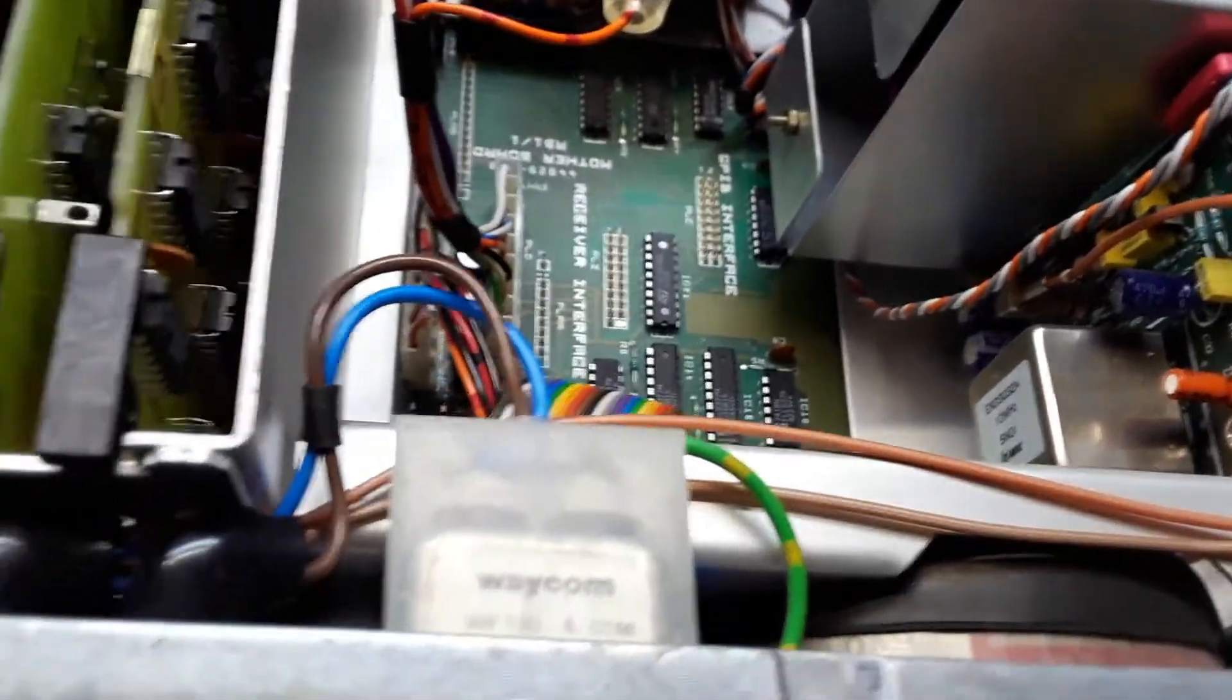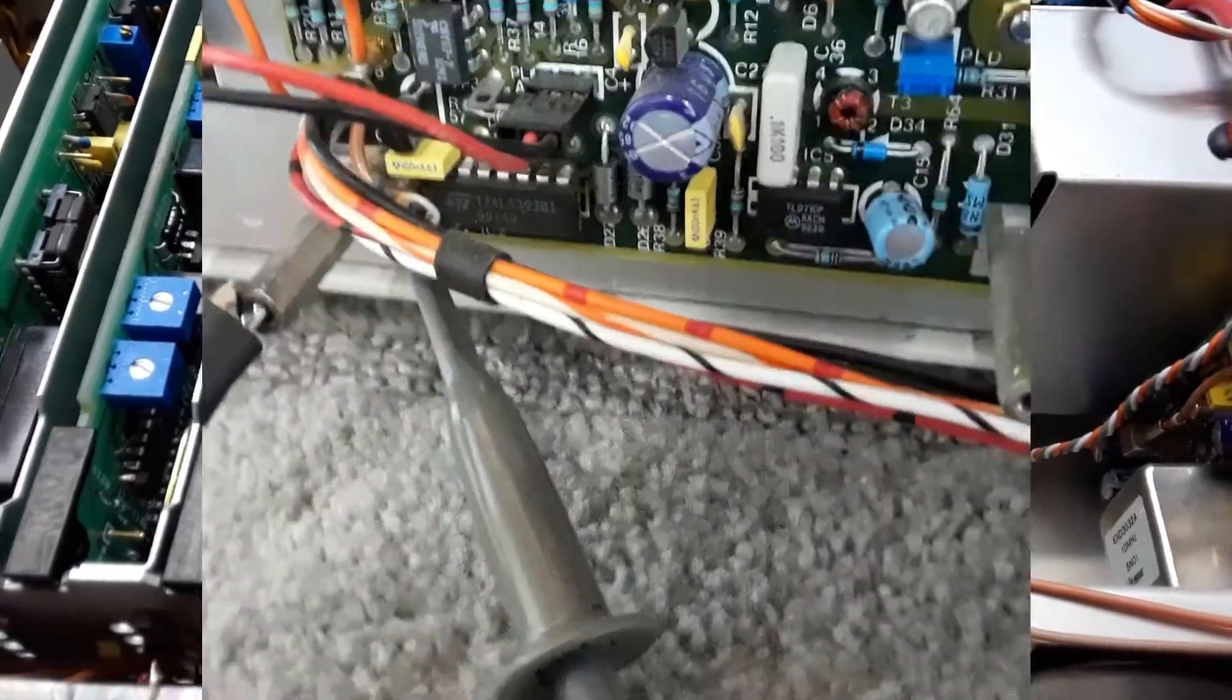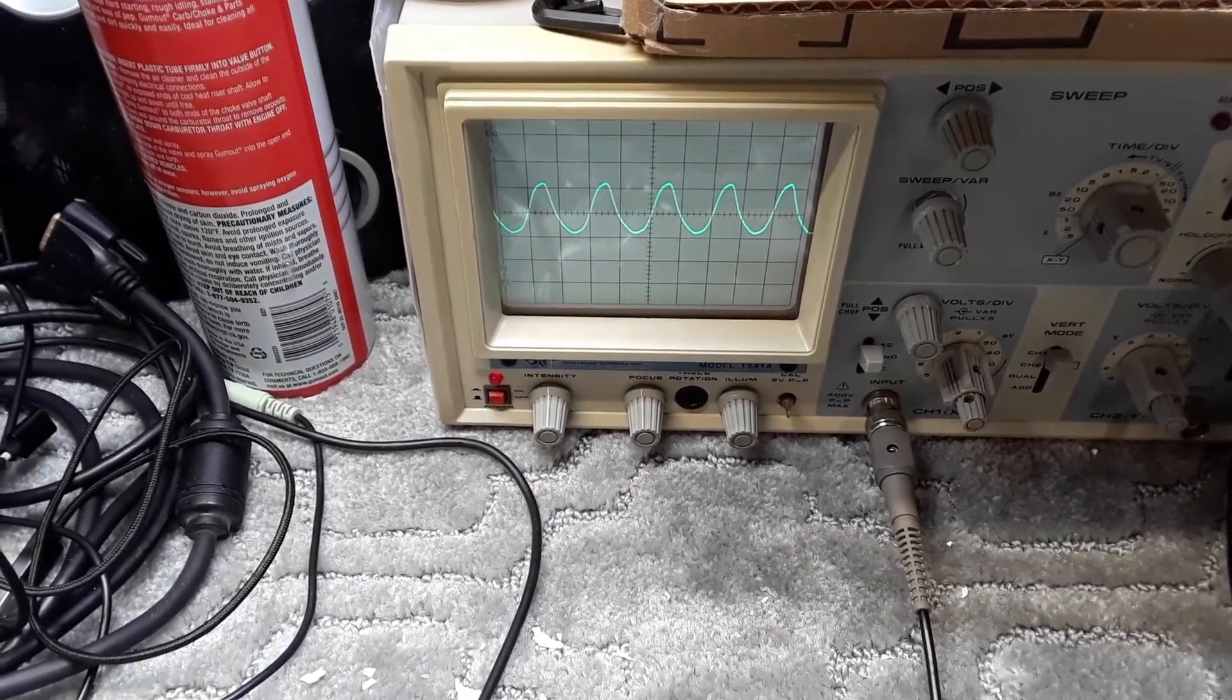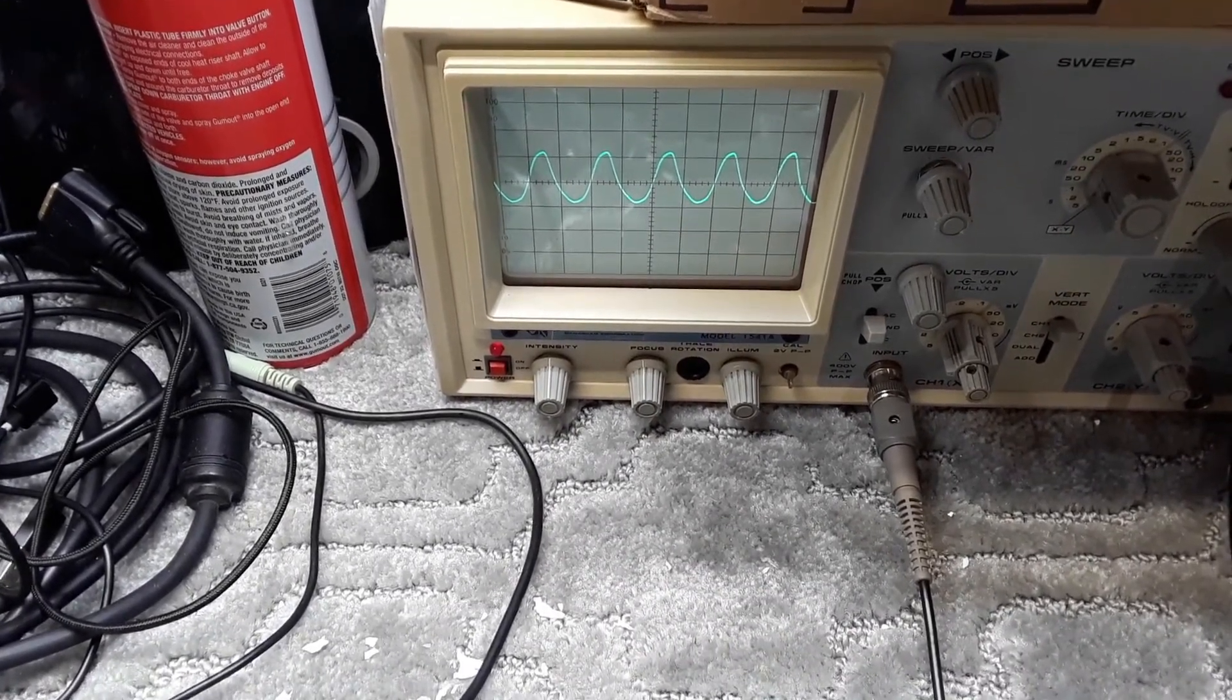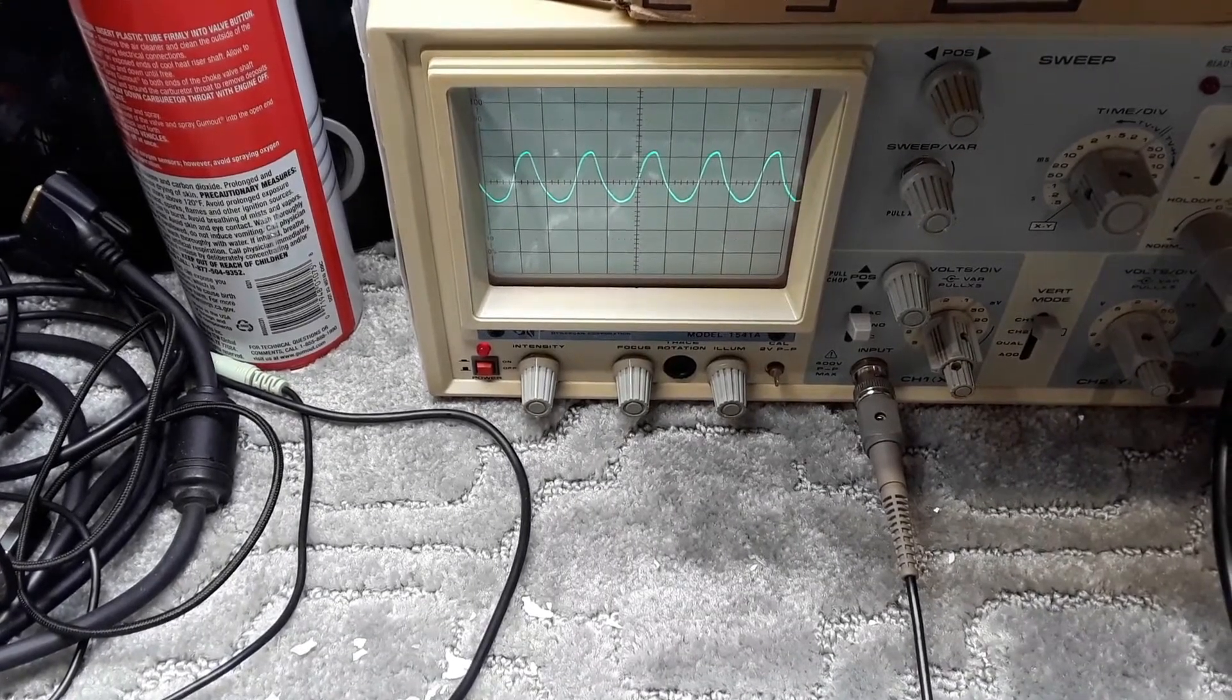I believe there are some stock faults with these caused by various electrolytic capacitors so I may have a look around the board here and see if I can see any other signs of capacitor failure. But for now it looks like we may have a working unit again. I just connected the scope down here onto that 10 meg oscillator signal and if you can see there that's the 10 meg oscillator running, feeding into the power supply. So the 10 meg signal is there, it's just not well connected so I'm going to solder that in place and then take a look see what's happening.